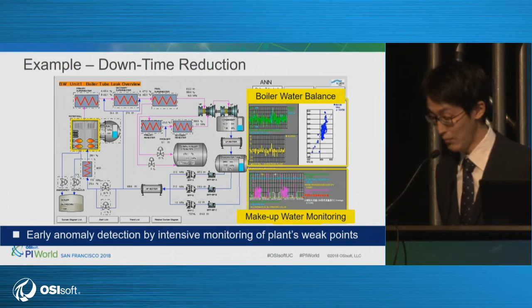This slide shows an example of intensive monitoring of boiler tube failures to reduce unplanned downtime and improve plant availability. Boiler tube failures are the leading cause of downtime for steam power plants. But by detecting leaks earlier, it is possible to prevent the expansion of the range to be repaired and to plan the repair work at the best possible time, resulting in reduced plant downtime.